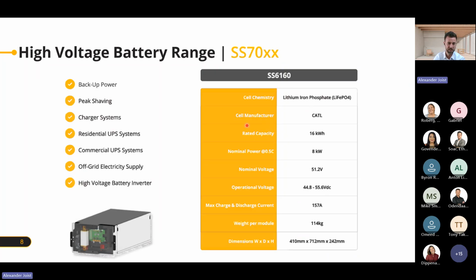If we look into more detail, as I said earlier already, the cell manufacturer is still CATL, 16 kilowatt hours of rated capacity. Then nominal power at 0.5C now is 8 kilowatt. Nominal voltage 51.2, operational voltage 44.8 to 55.6. And the max charge and discharge current is 157 amps, right?